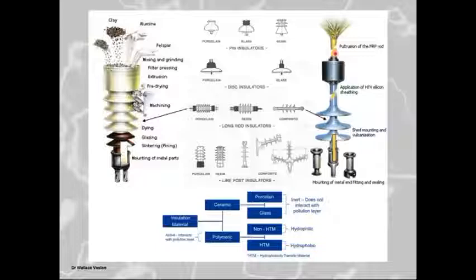And today you can get acid resistant rods with acid resistant resins, and all the issues surrounding them have been sorted out. Now, in this manufacturing process, they take this rod, they treat it with a bonding agent, and then a sheath is extruded onto it, at least 3 millimeters thick. This sheath is an HTV silicone rubber sheath, high temperature vulcanized.